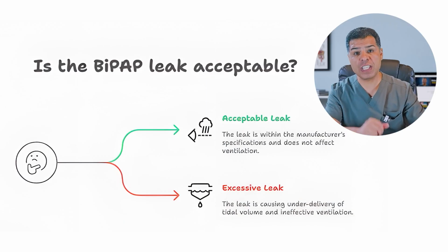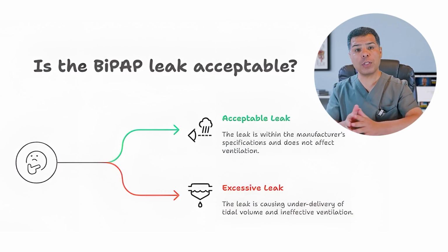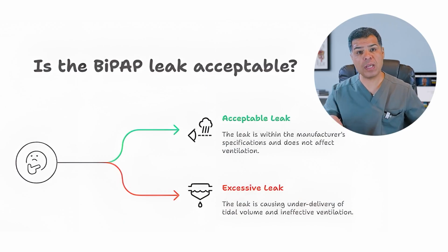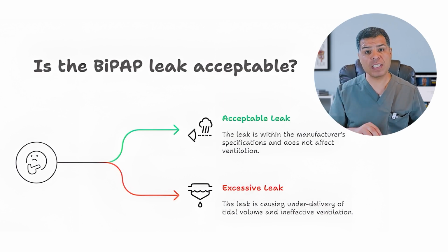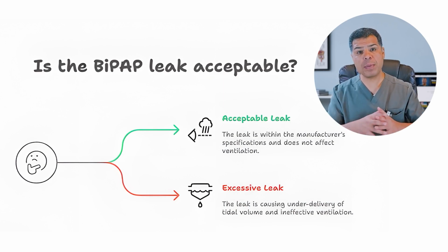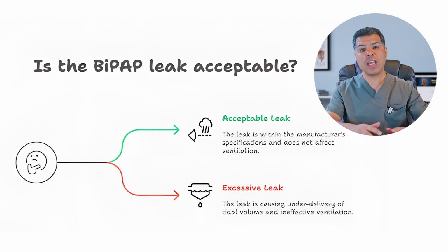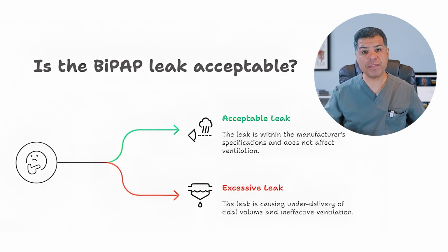Now, a quick note about the leak on BiPAP. All BiPAP systems are designed with a certain amount of intentional leak built into the circuit to prevent CO2 rebreathing. The exact amount of this intentional leak varies by the manufacturer and device design. In contrast, unintentional leak refers to unwanted air escape, usually from poor mask seal or mouth opening.